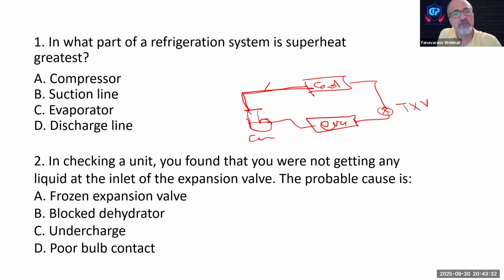But the answer for this question is compressor, because the temperature inside the compressor is always 50 degrees more than at the discharge line. If you have a thermometer and you measure, for example, 140 degrees Fahrenheit at the discharge line, let's go with the reciprocating compressor, the inside of the compressor is always 50 degrees higher. So the highest superheated gas is actually inside the compressor. So the answer for this question is A. Most of the guys think it's the discharge line, but the right answer is A.